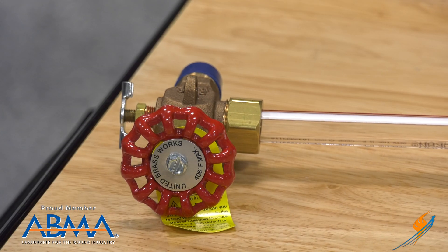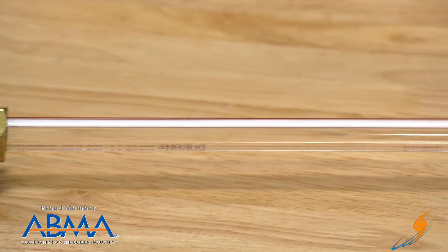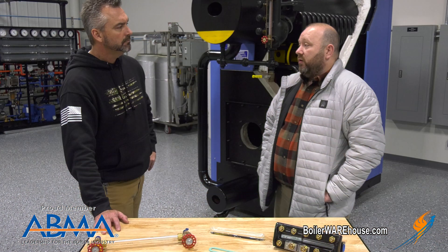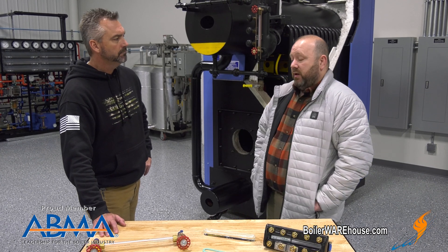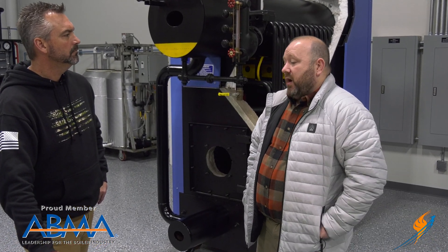So where would you use this? This is one of the most common and most economical solutions that you see in the boiler room. They go on small boilers up through some pretty large boilers. Manufacturers use them as an economical version — the McDonnell Miller is a common low water cutoff. So that's typically where you see these, on ranges up to really a couple hundred pounds.